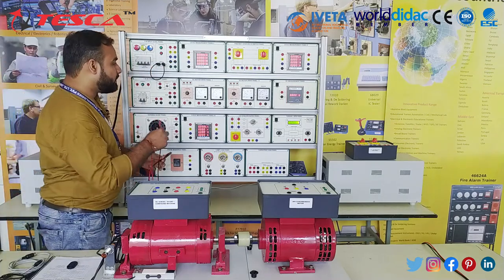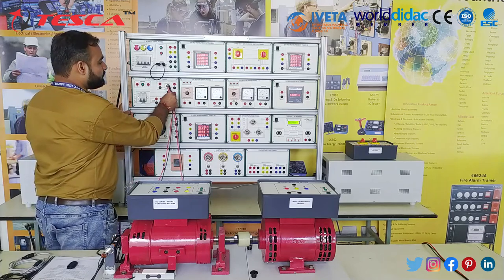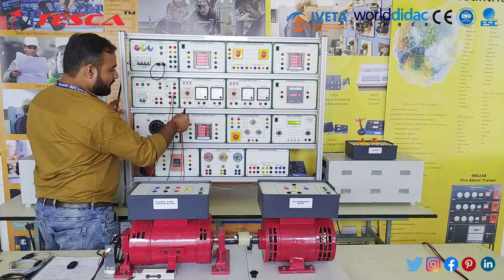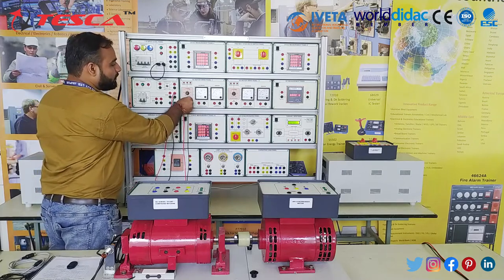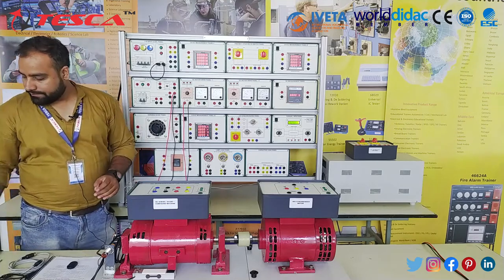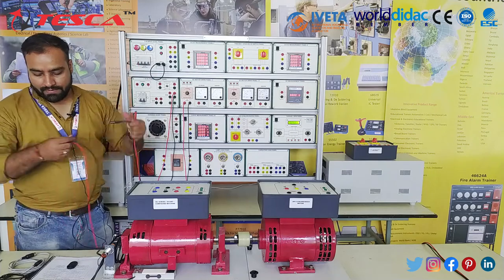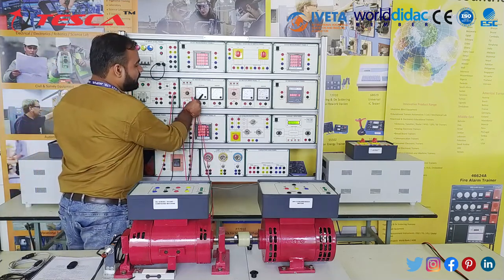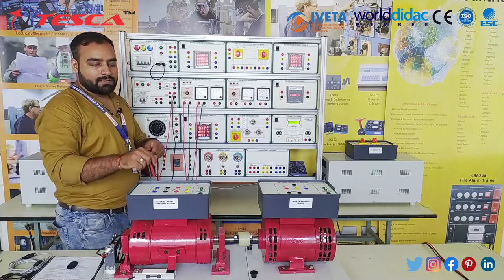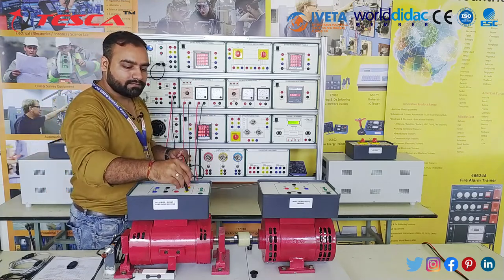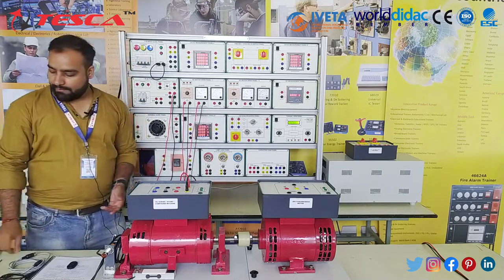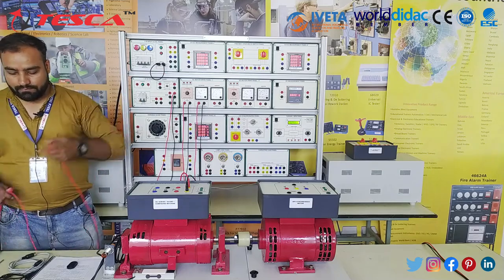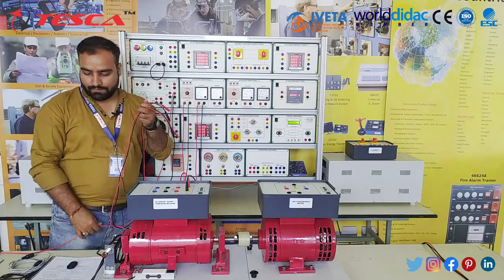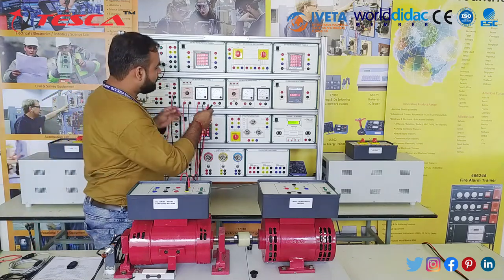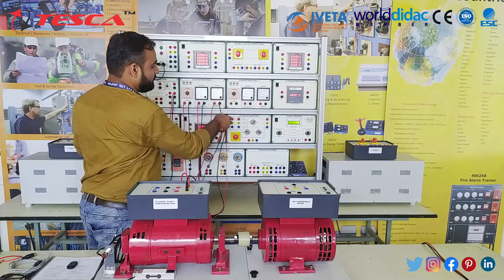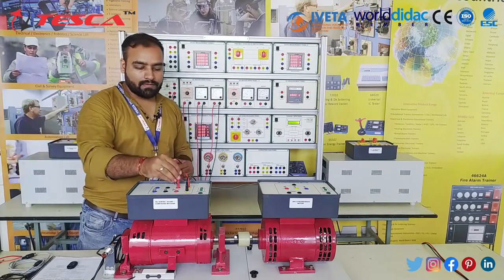First, we will provide single phase AC supply to the DC motor drive panel 1. Connect T12 and T14 from the MCB1 to T1 and T2 on the DC motor drive panel. Then we connect T3 and T4 to provide shunt field on F1 and F2 respectively. For providing armature voltages, we'll connect T5 and T6 on the armature.